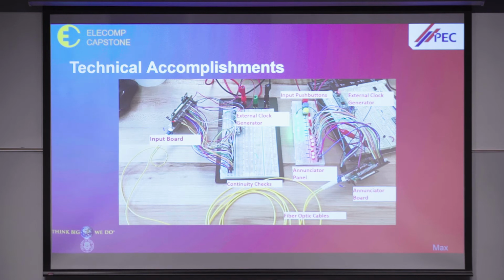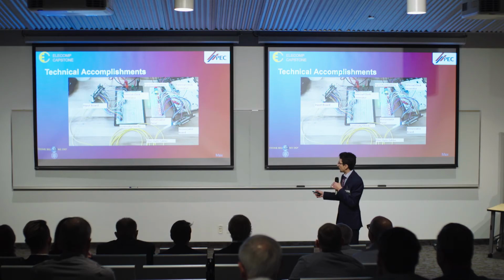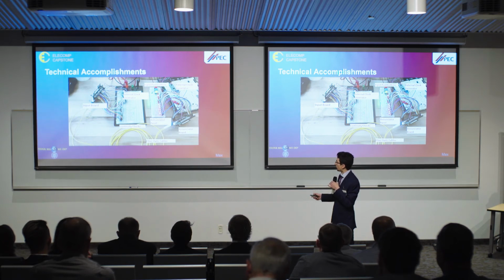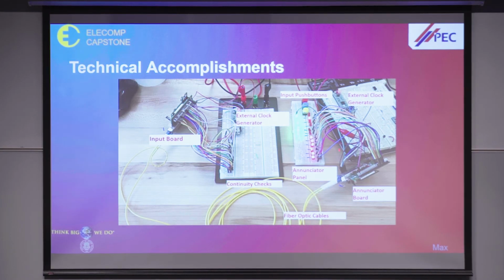These are being monitored by the input board, which performs continuity checks periodically. Then the state of each breaker is sent down through the fiber to the annunciator board, where that state is displayed on this LED panel.